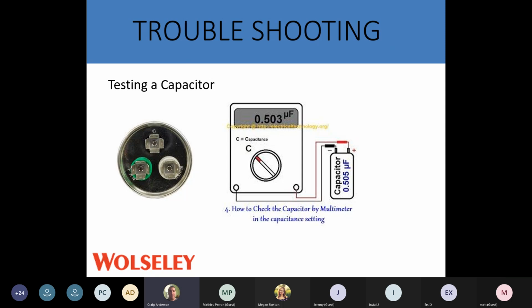Easiest thing to get out of the way if you have a multimeter, check your capacitor. The fan motor's not running, the compressor's not running. Test it with your multimeter. There were so many capacitors that used to come to our counter and they were fine. We'd sell the person the new capacitor because they wanted it. They'd throw the other one in the garbage. I used to reach out of the garbage, put it on the counter and test it with my amp probe. There was nothing wrong with it. Use your testers. Very easy to test.